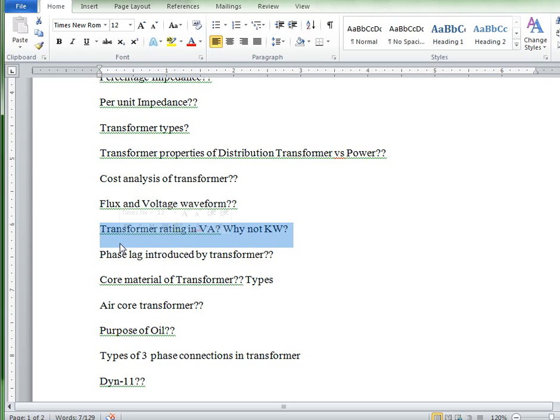Ye bada simple sa answer hai, hum transformer mein bhi aksar karte hain. Transformer is actually a series device. It takes power, converts it into a different voltage level if the turn ratio is different, and gives an output on the secondary side. But that series device has some active power losses (P) and reactive power losses (Q) both, so it takes a share of that power. Agar wo sirf resistive losses leti to hamare liye koi masla nahi tha, we could design it as kilowatt. But it takes P as well as Q, so we have to rate it according to some VA rating, KVA rating, or MVA rating.